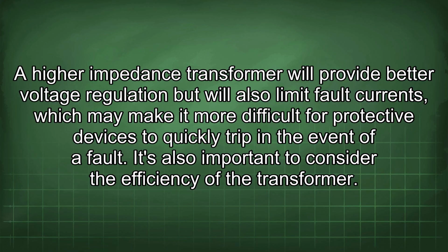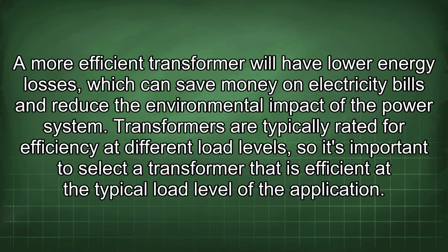It's also important to consider the efficiency of the transformer. A more efficient transformer will have lower energy losses, which can save money on electricity bills and reduce the environmental impact of the power system. Transformers are typically rated for efficiency at different load levels, so it's important to select a transformer that is efficient at the typical load level of the application.